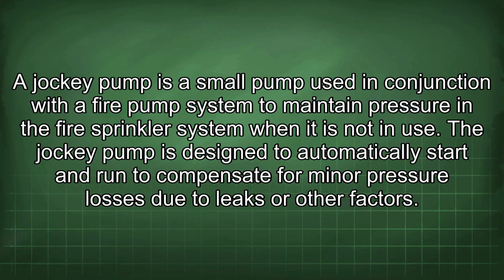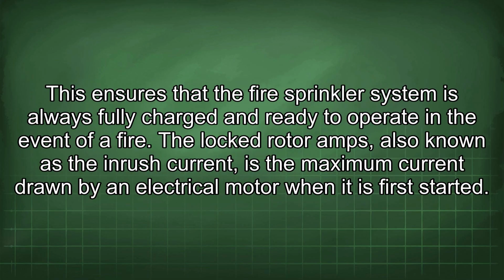A jockey pump is a small pump used in conjunction with a fire pump system to maintain pressure in the fire sprinkler system when it is not in use. The jockey pump is designed to automatically start and run to compensate for minor pressure losses due to leaks or other factors. This ensures that the fire sprinkler system is always fully charged and ready to operate in the event of a fire.